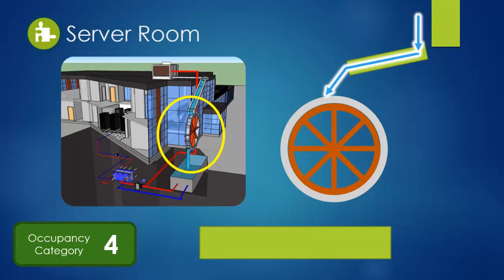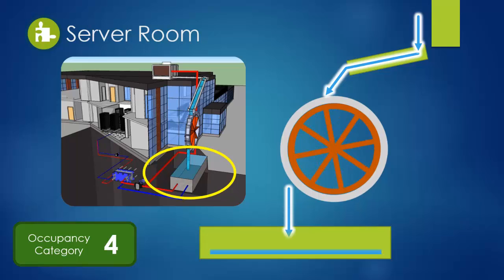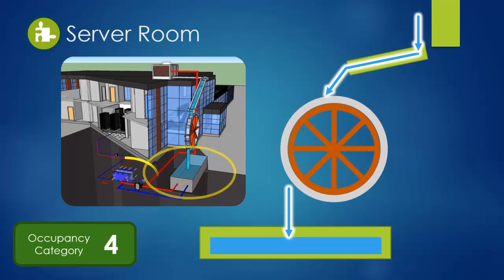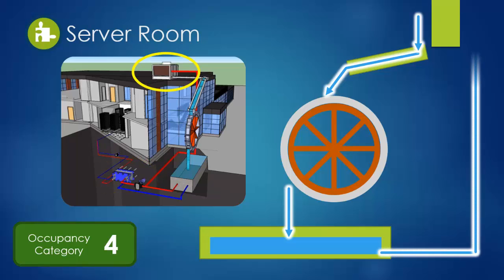The small amount of power generated from the turning of the wheel will assist in powering the pump. Next, the water will drop into a basin below and be piped to a heat exchanger. In the interior loop, water will flow through water-cooled server racks, absorbing heat and sending it back to the heat exchanger. The heat will be transferred to the exterior loop and the process will repeat.